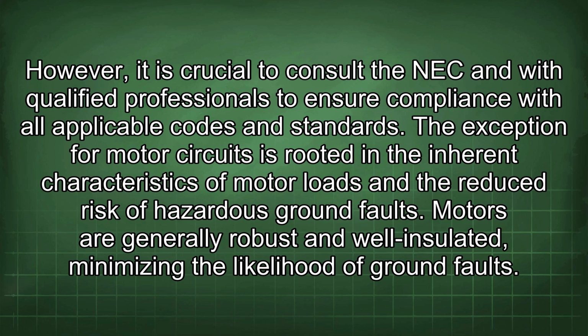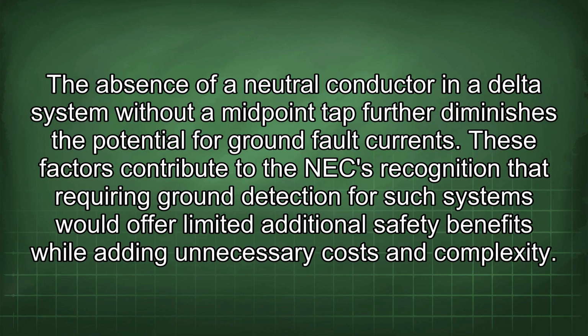Motors are generally robust and well insulated, minimizing the likelihood of ground faults. The absence of a neutral conductor in the delta system without a midpoint tap further diminishes the potential for ground fault currents. These factors contribute to the NEC recognition that requiring ground detection for such systems would offer limited additional safety benefits while adding unnecessary costs and complexity.